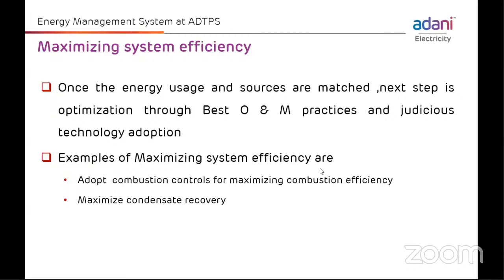Air means actually oxygen. Whenever there is a deficiency of oxygen or air, there is always incomplete combustion, which leads to losses. Or in other way, if you increase your airflow to the boiler, there is complete combustion, but there is excess air, which ultimately loads your fans to handle the flue gas. It will increase your auxiliary power consumption. So we should optimize in such a way that there should not be incomplete combustion, or there should not be any excess air to handle these gases, which ultimately increases our auxiliary power consumption.